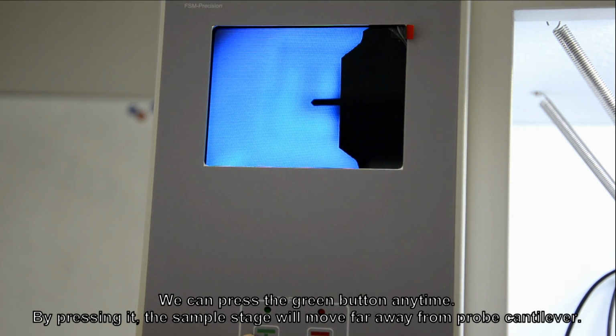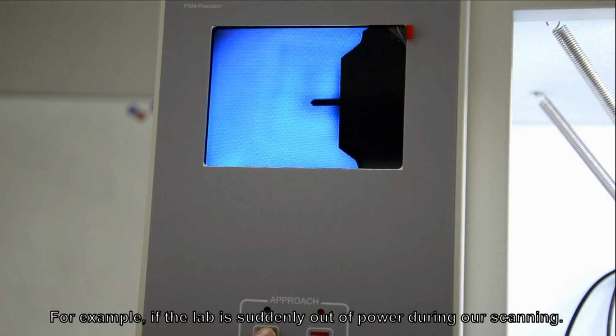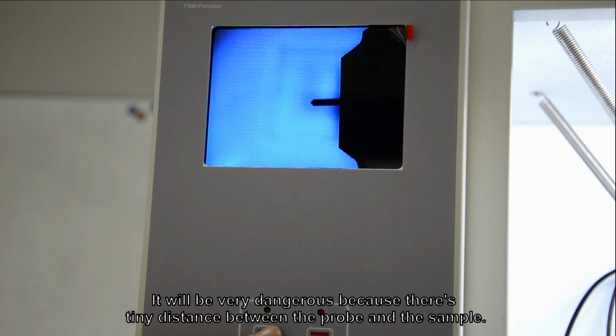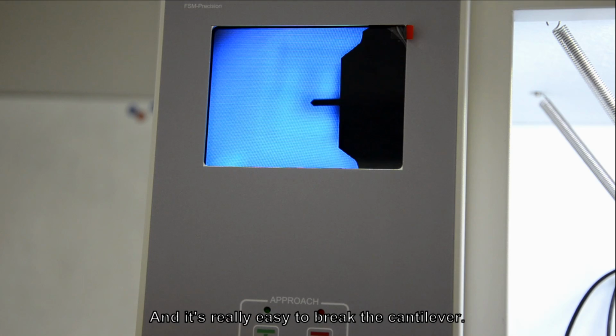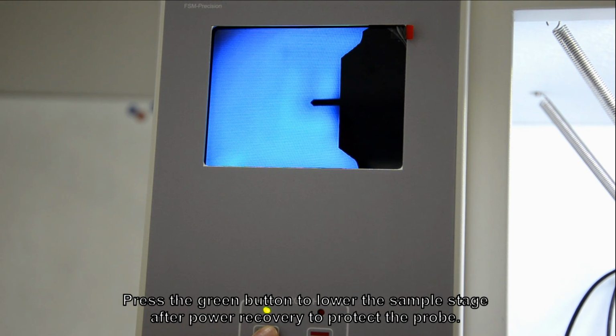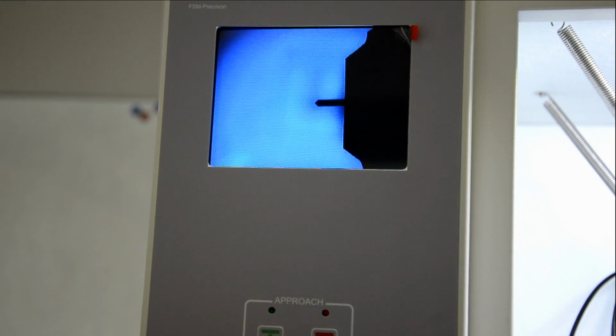We can press the green button anytime. By pressing it, the sample stage will move far away from probe cantilever. For example, if the lab is suddenly out of power during our scanning, it will be very dangerous because there's tiny distance between the probe and the sample, and it's really easy to break the cantilever. Press the green button to lower the sample stage after power recovery to protect the probe.